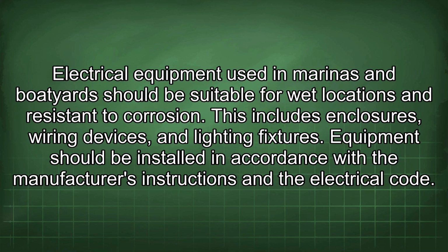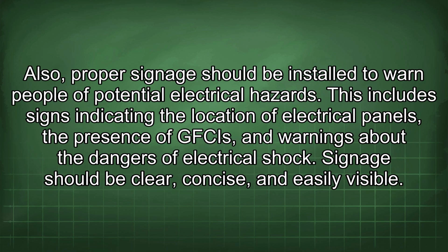Electrical equipment used in marinas and boatyards should be suitable for wet locations and resistant to corrosion. This includes enclosures, wiring devices, and lighting fixtures. Equipment should be installed in accordance with the manufacturer's instructions and the electrical code. Also, proper signage should be installed to warn people of potential electrical hazards. This includes signs indicating the location of electrical panels, the presence of GFCIs, and warnings about the dangers of electrical shock. Signage should be clear, concise, and easily visible.